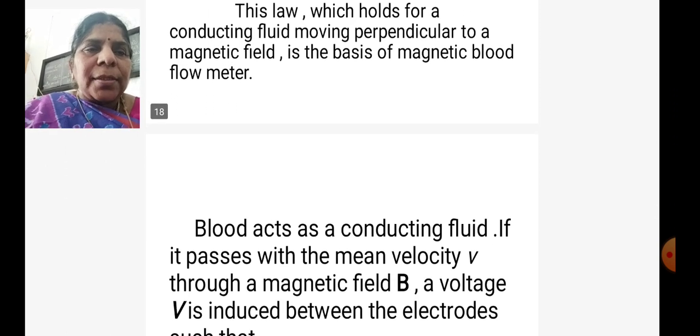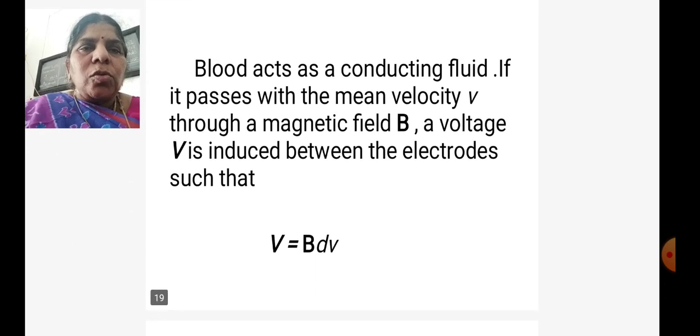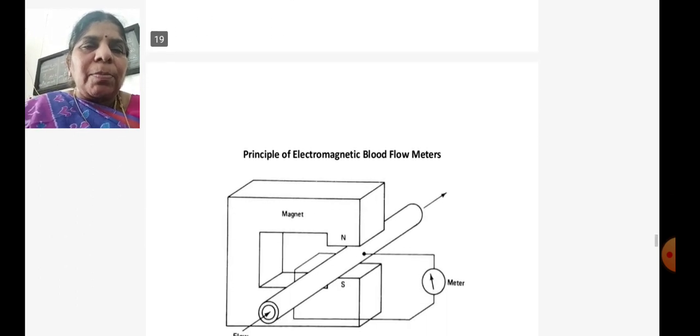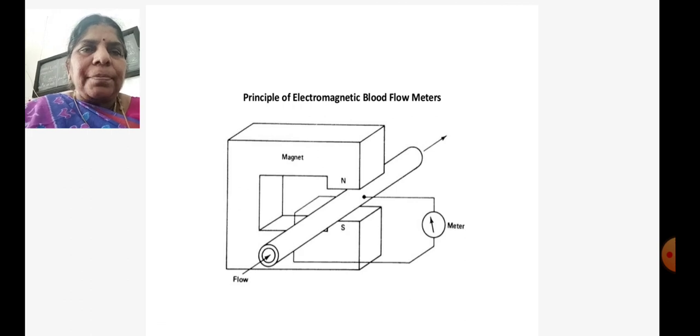Here, blood acts as a conducting fluid that moves with velocity v through a magnetic field B. An induced voltage V is applied between electrodes such that the induced voltage will produce a small voltage equal to BDv, where D is the diameter of the blood vessel. You can see the diagram.